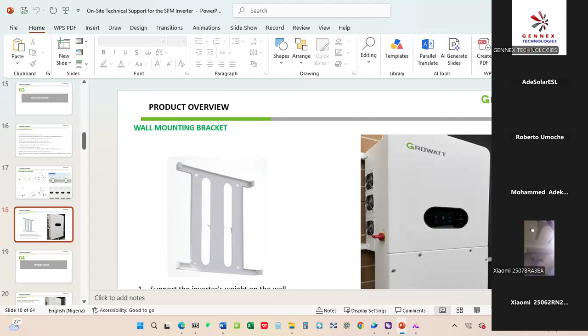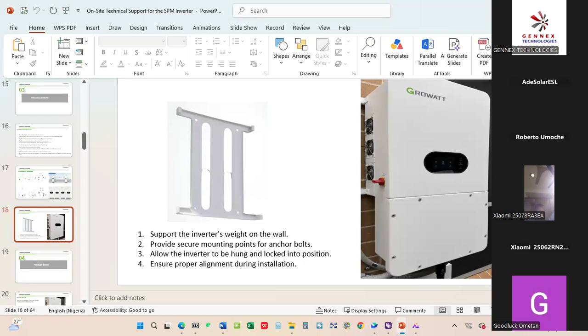So, like I said, the wall bracket here supports the inverter on the wall so that it will not fall because of the weight of this inverter. Then it allows the inverter to be locked into position. It allows the inverter to be placed either horizontally or vertically, but it's always advisable to place this inverter vertically. Then it also ensures proper alignment during installation. It gives you the edge to be able to terminate all your cables: your PV cable, your grid, and your load cable.